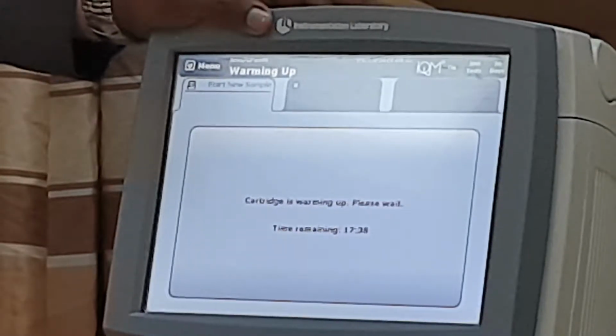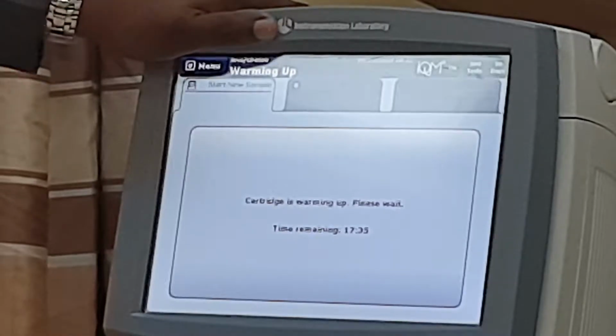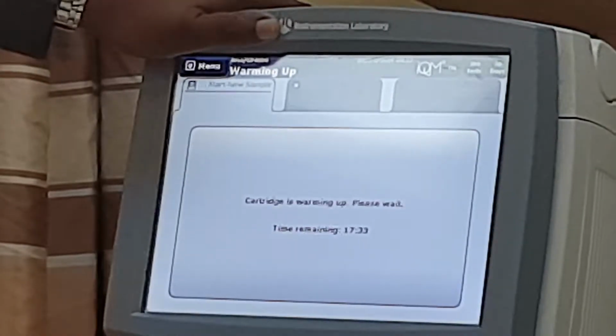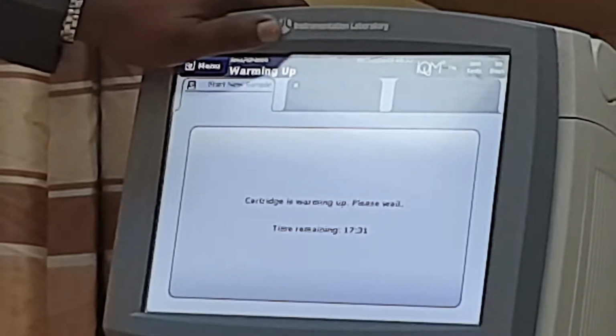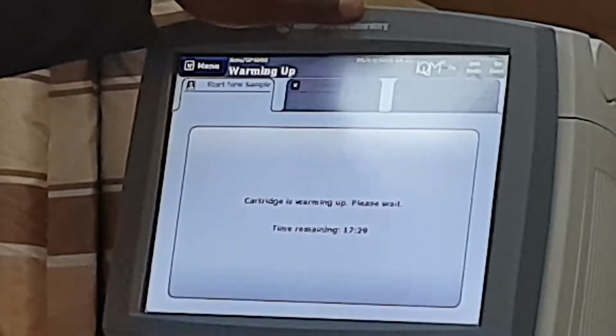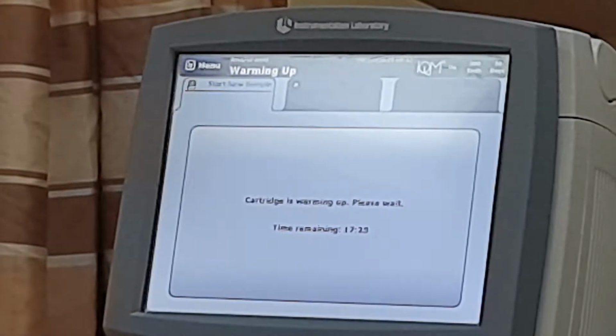After that, we go to the calibration. We have 4 levels of calibration, which we call CVP. CVP is an abbreviation of calibration, verification, product. We have 4 levels of CVP. I will start with 1 and 2, low and high co-oximetry parameters, and 3 and 4, low and high hematocrit.